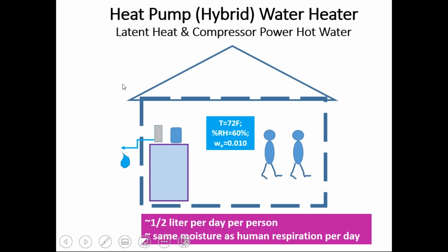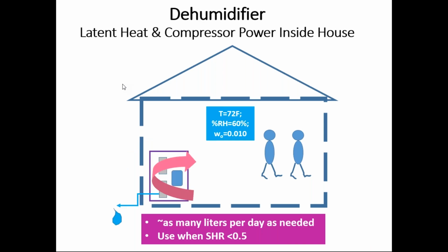And when we look at hybrid or heat pump water heaters, these scale with the number of people in a home and their shower activity. And basically, from our field data, we find that a typical heat pump water heater pulls out about half a liter per day per person. If there's no one in the house, no hot water is needed. It pulls out very little moisture. When a lot of people are in the home, it increases. So it scales nicely with occupancy, and we'll see that in the field data.